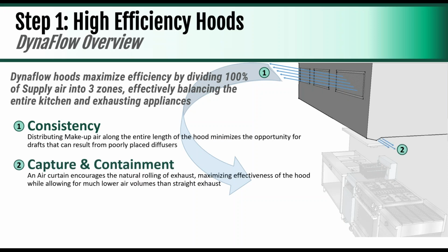The second and most important for a high efficiency hood is the capture and containment. This is actually an air curtain that blows down and slightly at an angle towards the appliances, so that as smoke rolls up into the hood, typically it's coming up along the back wall and it rolls back towards the top of the hood. That capture and containment air curtain pushes it back into the hood so it continues to roll as it's being extracted at lower volumes than a non-high efficiency hood.